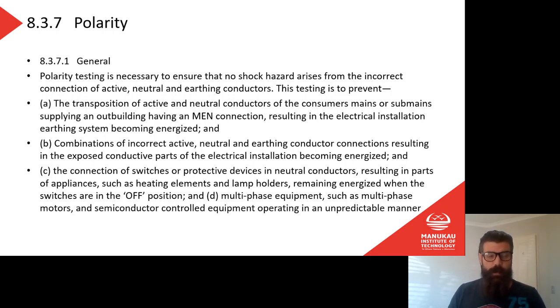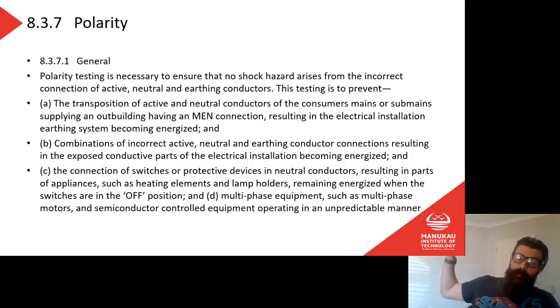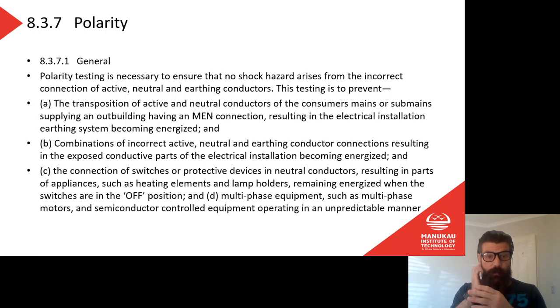So phase and neutral won't change, or it doesn't matter if I change the phase and neutral from an operational point of view. What I don't want to do is put my switch in the neutral conductor instead of the phase, because then when I switch that light switch off, I'm breaking the neutral conductor. So everything on the phase line is still live up to that switch. That means I will have live voltage at my light. The light won't be going, but there'll be 230 volts there even though the switch is switched off, because the switch is in the neutral instead of the phase. So that could cause someone to get an electric shock when they're changing a light bulb, for example.